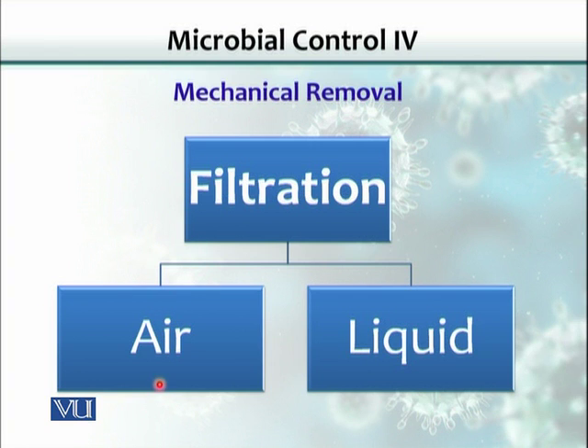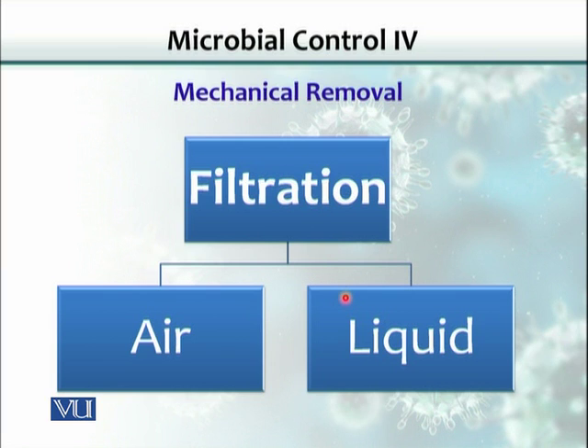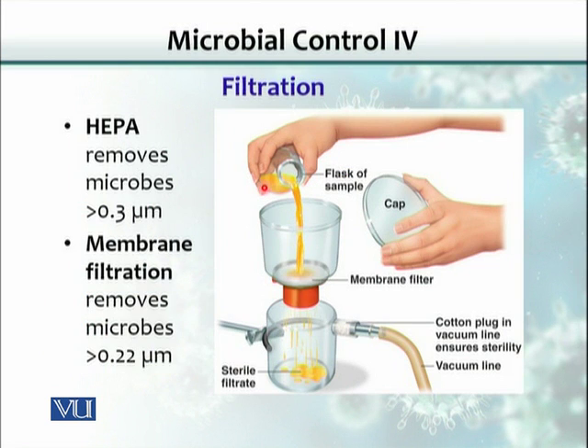Air could be filtered. In situations where we need air to be completely free from organisms, such as when culturing cells, a large cabinet-type instrument on a table blows filtered air. Inside that instrument is a HEPA filter — a high-efficiency particulate air filter — which removes particles larger than 0.3 microns. Similarly, liquids can be filtered through membranes to sterilize or eliminate organisms. These are called membrane filters, and the fluid is passed through them. The porosity of the filter prevents organisms from passing through, yielding sterile filtrate.